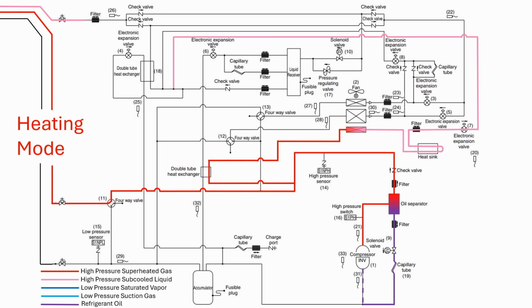When the refrigerant re-enters the outdoor unit on the liquid line, it is routed through a series of check valves to the liquid receiver. The liquid refrigerant leaving the receiver meets up with the liquid refrigerant from the 3rd compartment of the heat exchanger and is then routed to the electronic expansion valves just ahead of the other 2 compartments in the outdoor heat exchanger. The electronic expansion valves meter the refrigerant, causing a pressure drop and changing the state of the refrigerant from a liquid to a low-pressure saturated vapor.